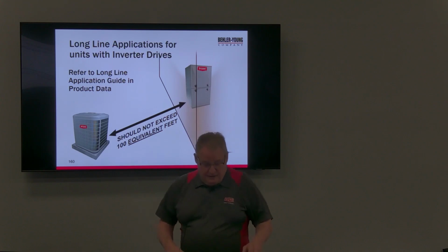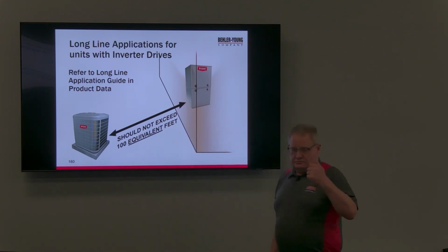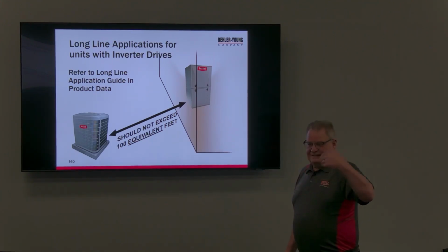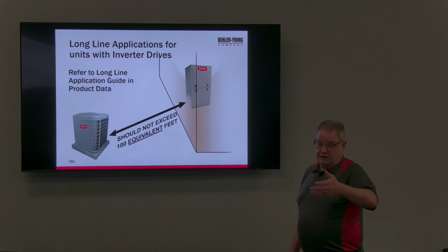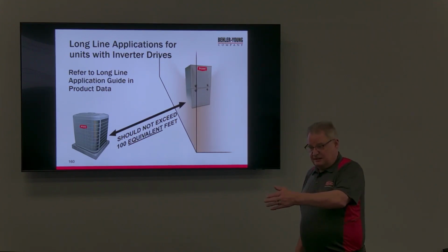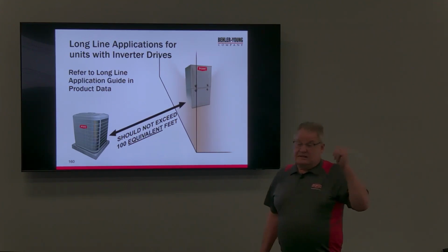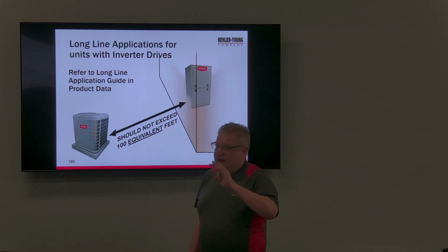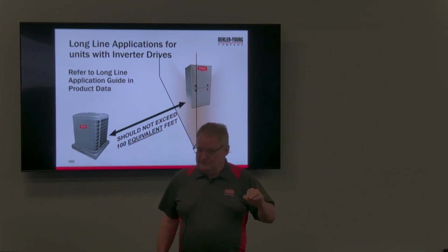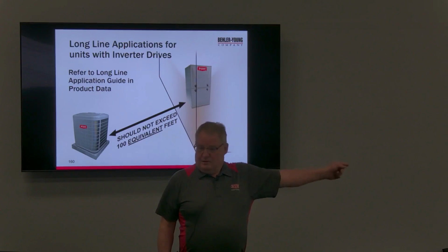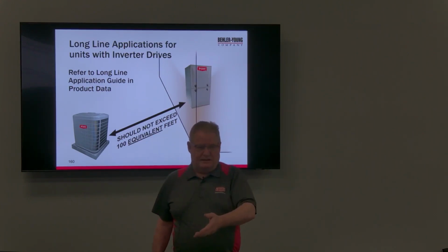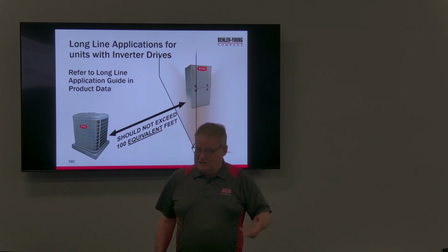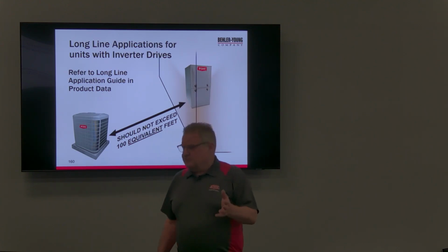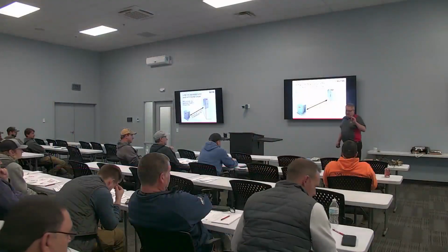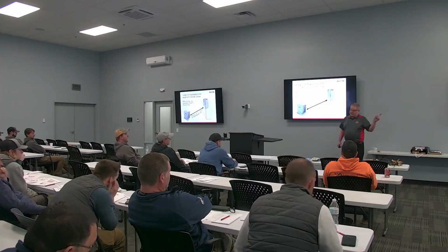That might be okay. So again, if you're going long line lengths, we want to get the long line guide and see if I need to upsize anything. Mini splits: the line set size is the line set size. There are no exceptions. So that head has 1/4, 3/8 in it. You are running 1/4, 3/8. And if you're replacing another head that was 1/4, half, you're changing the line set. There's no exceptions. Mini splits are very critically charged. Line set has to match the indoor head size.